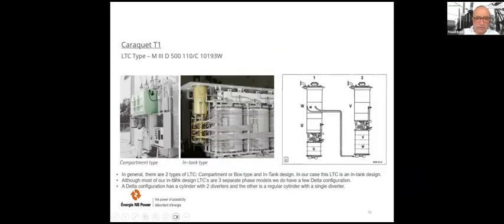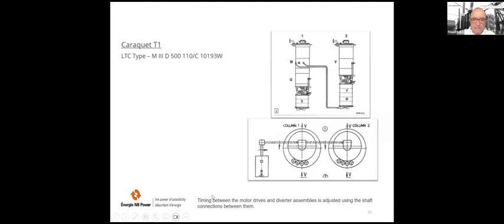So in general, there are two types of LTC, compartment of box type and in-tank design. In our case, this LTC is an in-tank design. Although most of our in-tank design LTCs are 3 separate phase models, we do have a few delta configuration, and the delta configuration has a cylinder with 2 diverters, and the other is a regular cylinder with a single diverter that you can see on the right picture. And timing between the motor drives and diverter assemblies is adjusted using the shaft connections between them.